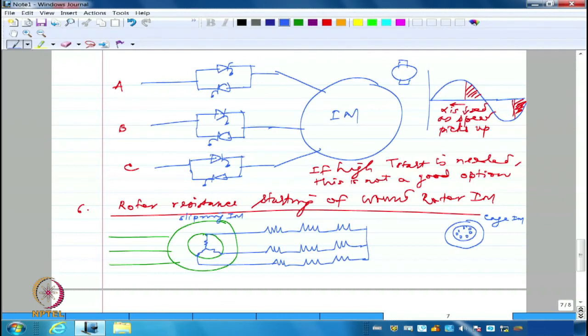So I will normally have contactors connected across each of these resistances, which can be closed as the machine gains speed further. I'm just showing contactors for each of these resistances. Similarly, I will have contactors for the next resistances as well, which will be closed as the motor gains velocity further and further.